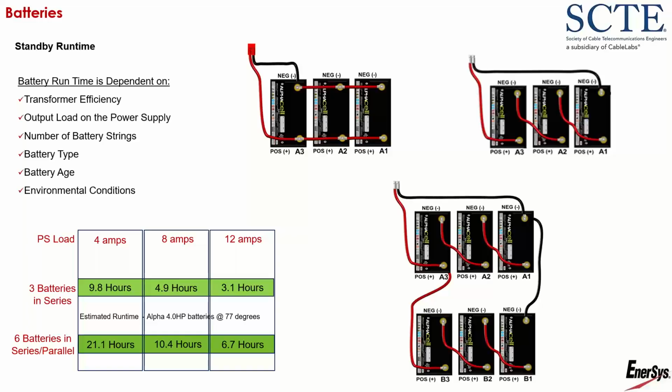Yeah, and there are some manufacturers that did power their transponders with the batteries. We did a long time ago too, and like I said, we currently do have one that works that way. And like I said, if Larry sends me an email, I can find out which pin that is. But most of the new transponders and new power supplies, all of our newer stuff, we do not use the battery string to power. We power through the interface between the transponder and the inverter.